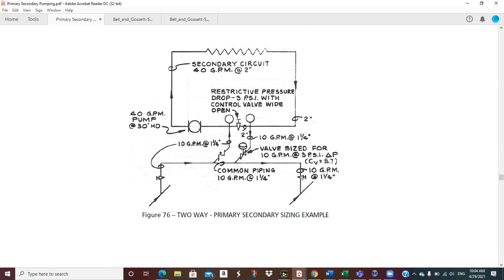So we've got 10 GPM through the crossover, kind of our typical heating example. So we've got 1 1/4 inch pipe, 1 1/4 inch bleed riser and bleed return. We've got 40 GPM, so that's our 2-inch pipe in the secondary. And notice he's specing a valve size for 10 GPM at 3 PSI drop, okay? And so 10 GPM, 3 PSI, so you can calculate your CV from that, right? 3 PSI, take the square root of that and divide it into 10, and I suspect you're going to get 5.7.